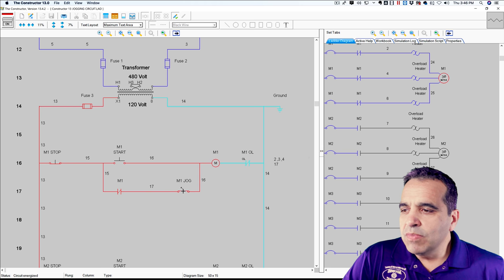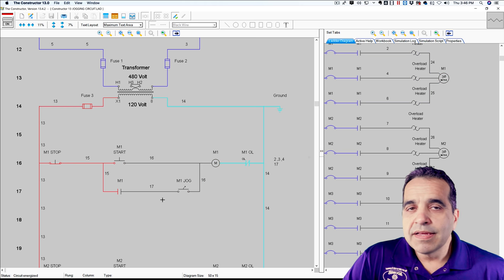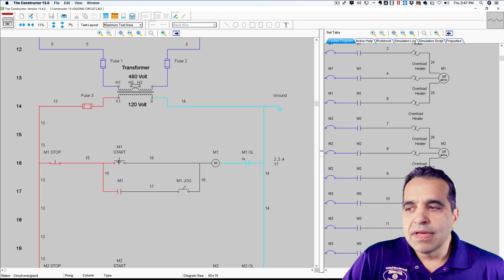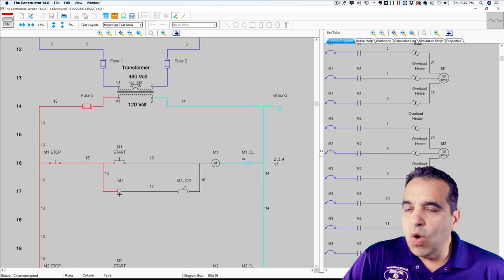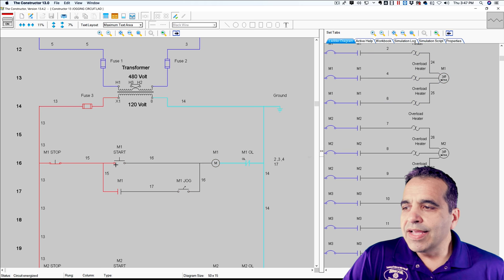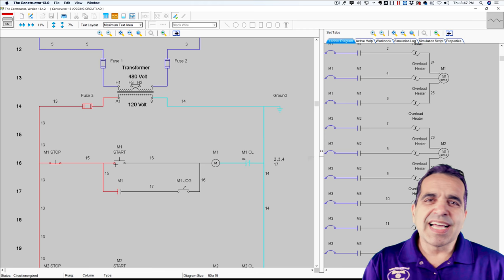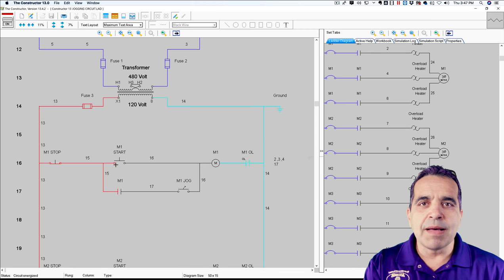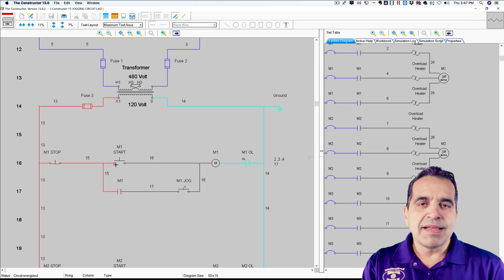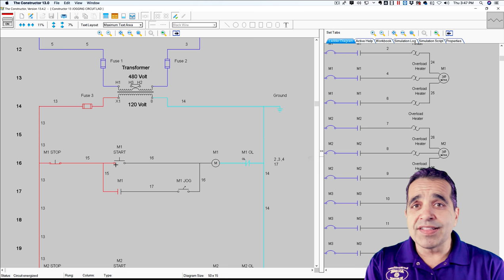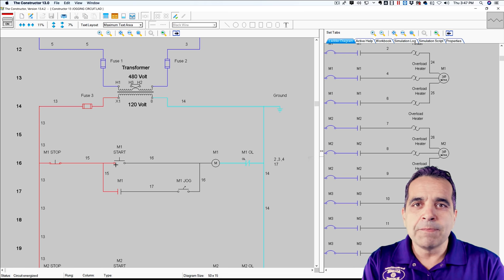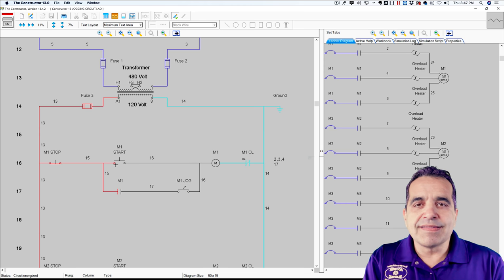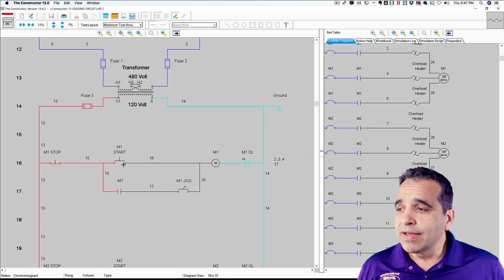So if I turn the motor on and I flip that switch off, the motor won't run, but now I can use the start button as a jog button. By putting this switch here, I have eliminated the holding circuit in the coil and I can use my start button to jog the motor. Now, sometimes this is used for like on a conveyor system. If you want to line something up to another piece of equipment or to a photo eye or anything like that, if you want to line something up in order to get the system to start in a certain position, a lot of times you'll need to jog that conveyor into place. And this is one of the ways that you can do it.